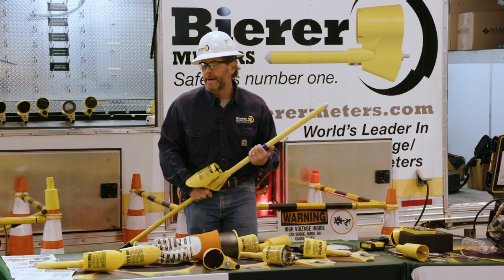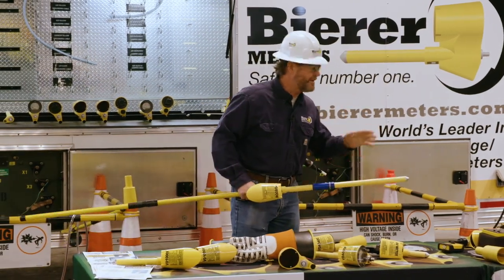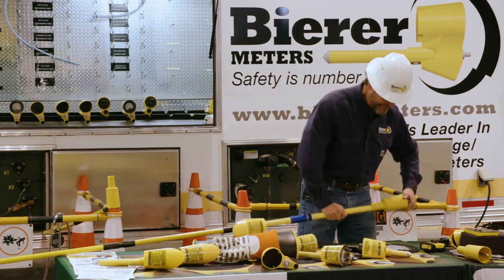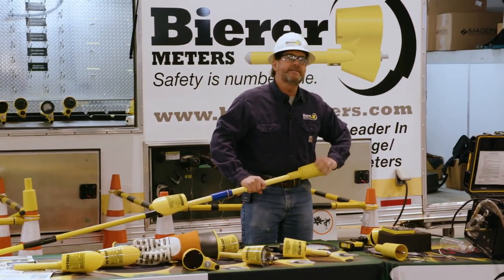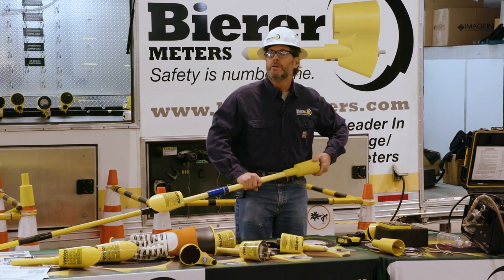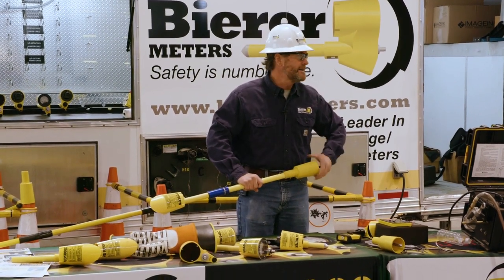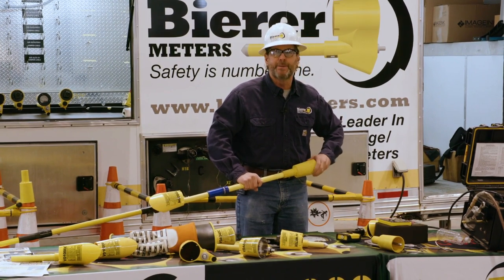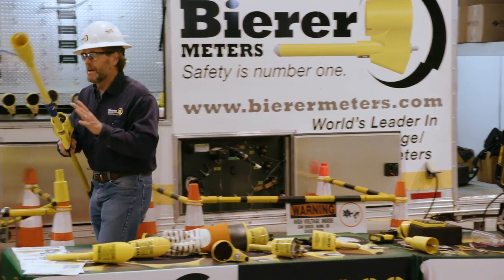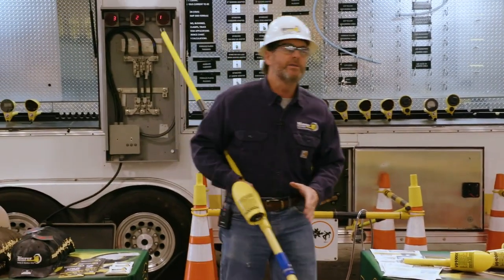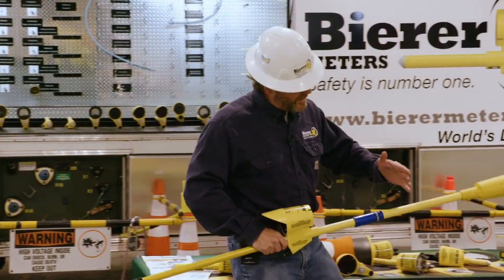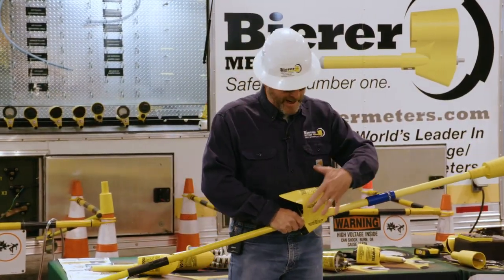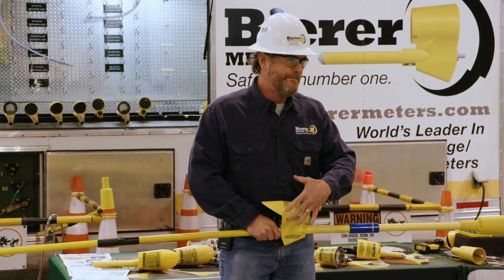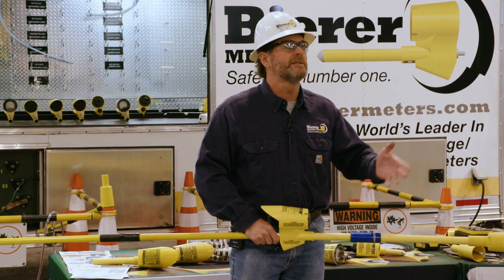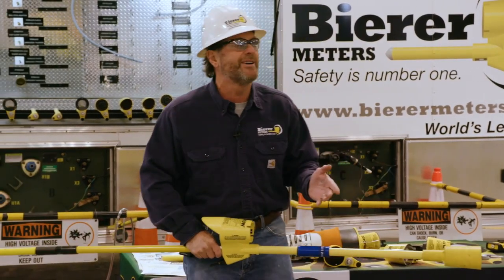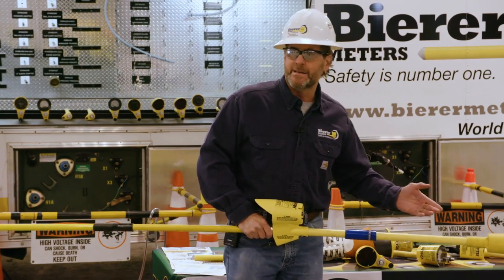So what we're gonna talk about, there's gonna be some situation scenarios where you're gonna visually inspect your work area. What's gonna happen is you're gonna see that if you use your phasing tool, your voltage indicator, corded or wireless, that you have an issue, you have a cabinet close by. You got a bleed wire that's close by. Maybe you're doing a substation, and if you use your tool and make contact with the conductor, there might be another hot phase nearby the meter head. You don't wanna have that situation because the opportunity for an arc flash is very high.